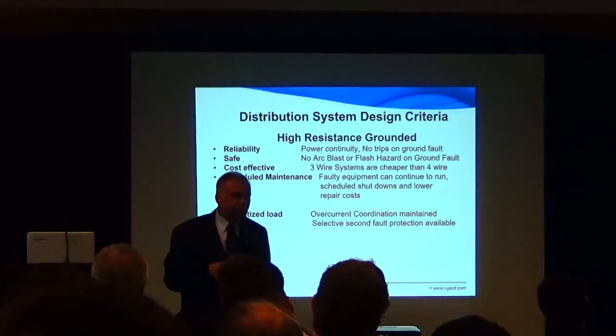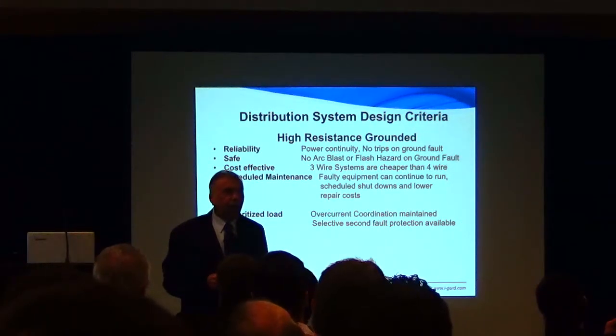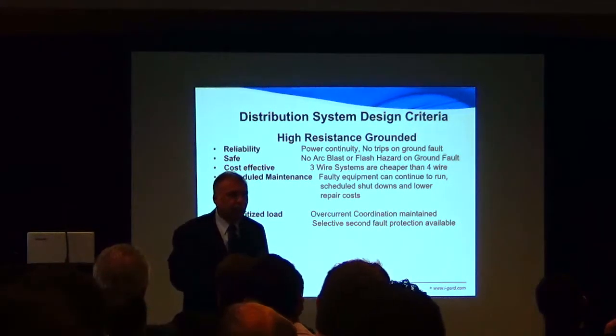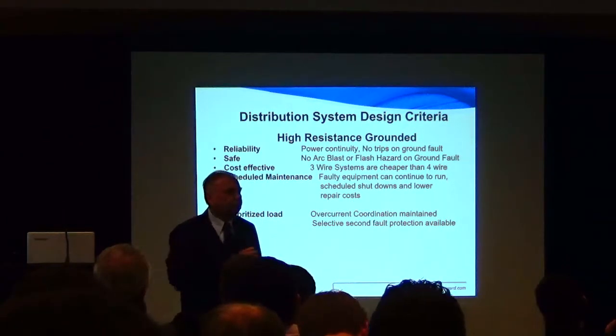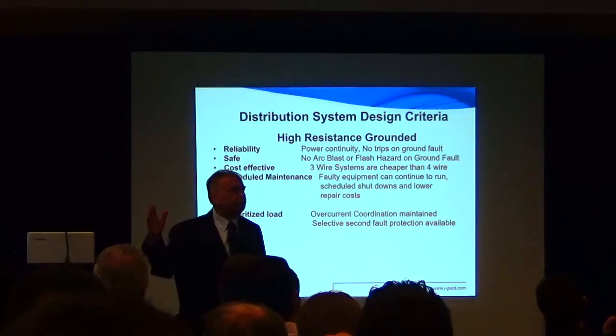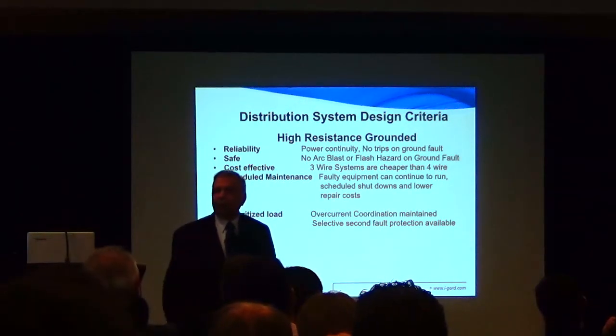No termination, no lugs for the neutral. Labor cost reduces, and the conduit size reduces. You only have three conductors rather than four conductors. So there is an across the board cost reduction of 25%, including all the other effects that come into it.